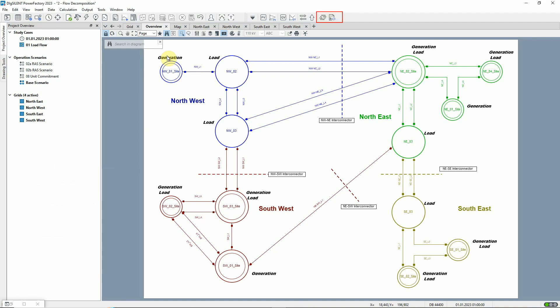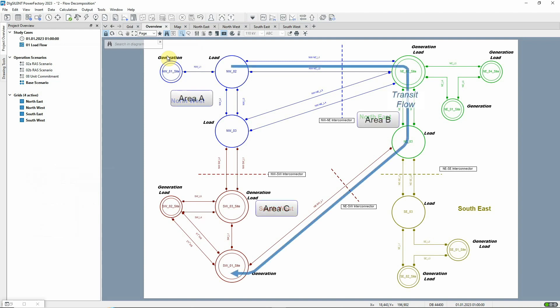The flow decomposition command can be used when evaluating flows between adjacent grids or operational areas. System operators need to determine the extent of transit flows in the network, power that flows from area A to area C, merely passing through area B.